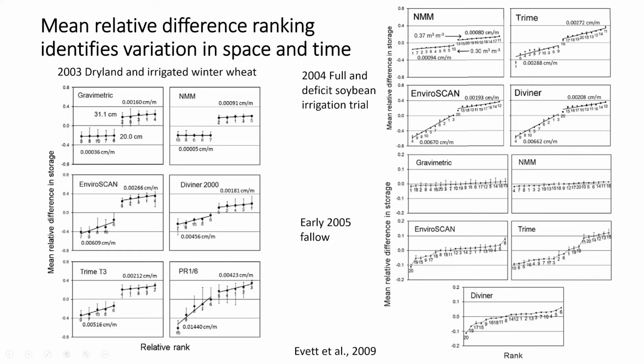The Diviner is a higher frequency device than an EnviroScan and should be a little less sensitive to these EM variations. The TRIME and the PR16 both showed more variability on the dry side than actually existed in the field by measurement. We repeated this in 2004 in a soybean field that was fully irrigated on the right side, and deficit irrigated in half of it, 10 access tubes in each half. The neutron moisture meter showed this kind of variability. The TRIME showed somewhat more. Here's some of the TRIME points way down here, falling off.